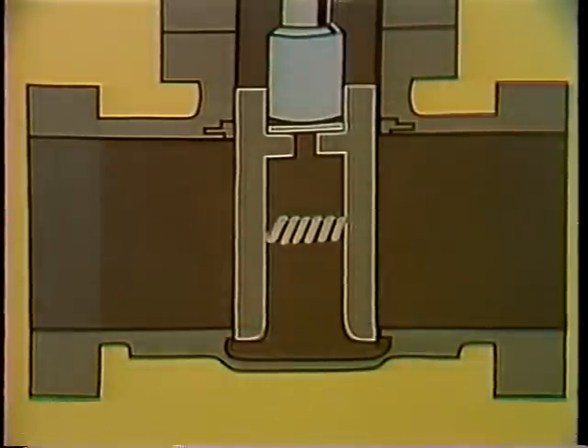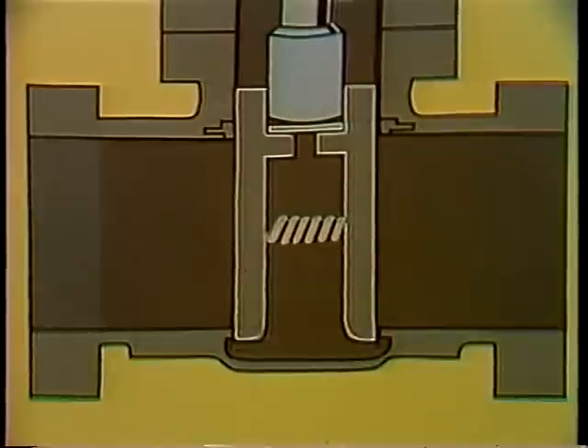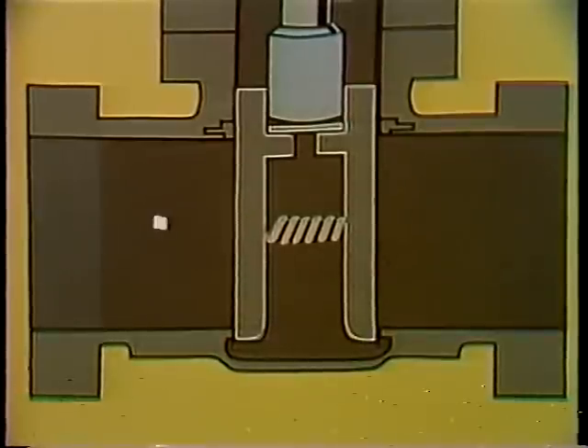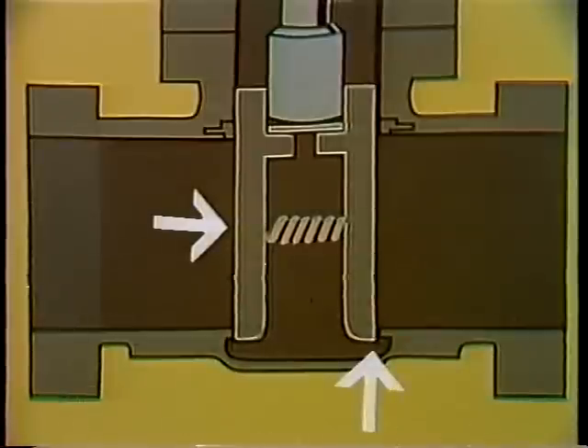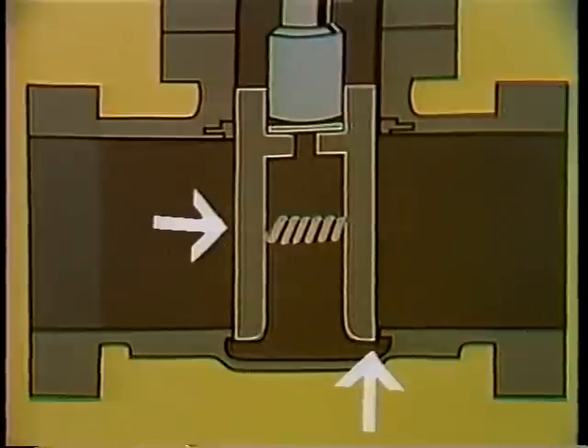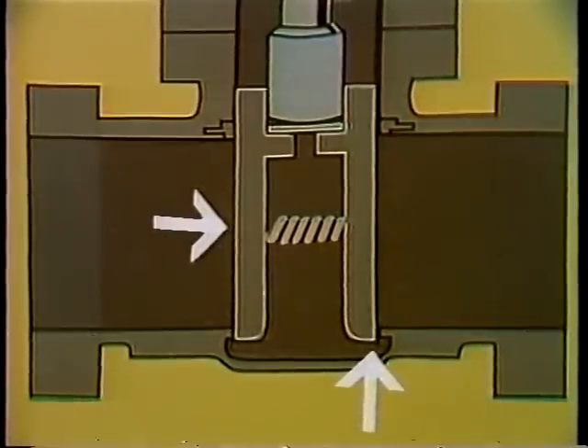Instead of wedging action, the double disk is seated by system pressure. Pressure from the high pressure side causes the disk on the low pressure side to seat tightly. This means it can be used for high temperature applications — the double disk will not jam as its metal expands under increasing temperature conditions.